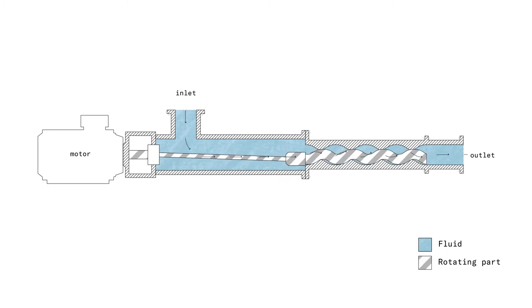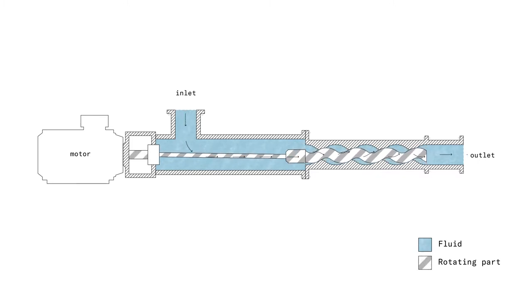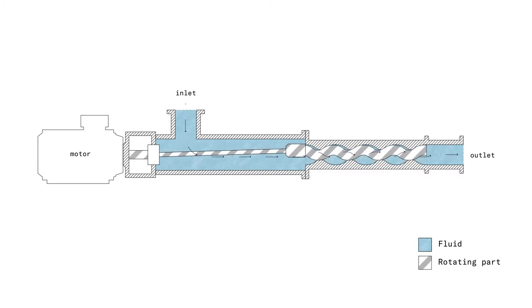What we see here is there is a cavity volume change. While it is rotating, we see that the liquid volume in the chamber is moving from small to big and big to small. If we look at these dimensions very carefully, first it is big and then slowly it moves over to small, and it pushes the liquid from left to the right. This is the motion that the liquid goes through the pump — it's being sucked in when the cavity is large, going to small, and being pushed to the right side.